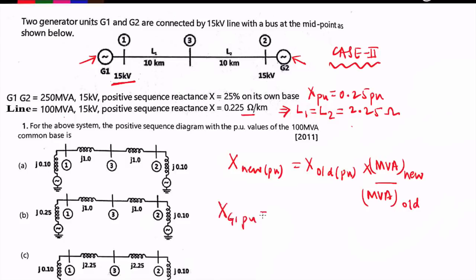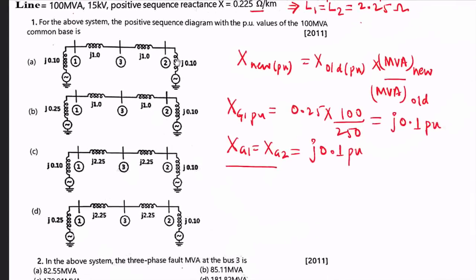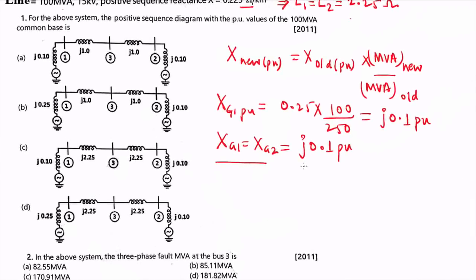So Xg1 (pu) on the new 100 MVA base = 0.25 × (100 / 250) = j0.1 pu. Since G2 has the same rating and same old reactance value, Xg2 = j0.1 pu as well. Looking at the options, only options A and C have generator reactance of 0.1 pu, so options B and D are eliminated.